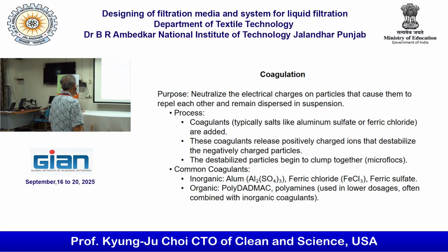The coagulant, typically a salt like aluminum sulfate or ferric chloride, is added. These coagulants release positively charged ions that destabilize the negatively charged particles. These destabilized particles begin to clump together, forming microflocs.